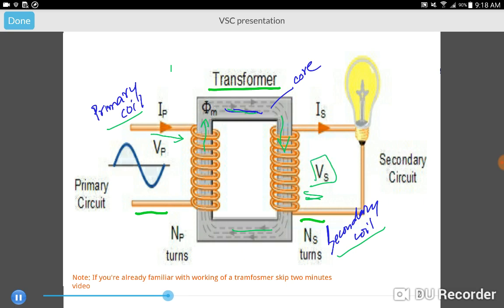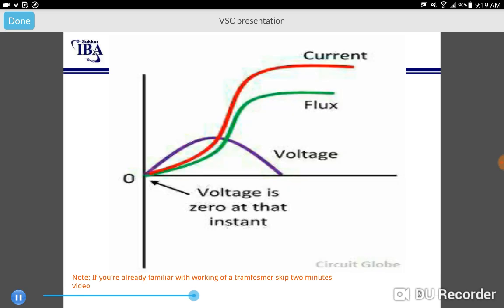The amount of induced voltage will be determined by Faraday's law, which says that induced voltage is equal to the number of turns multiplied by the rate of change of flux. As we see here, the rate of change of flux is directly proportional to the voltage, or we can say that the flux is the integral of this voltage. In a continuously operating transformer, the flux waveform and the induced voltage waveform are shifted by 90 degrees, but a significant difference exists between the continuous mode operation and the energization of the transformer. This can be further demonstrated here.